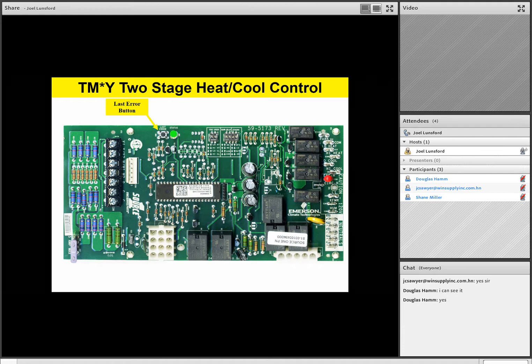Right next to the last error button, you'll find that it has a status LED. It's going to be the same thing. It'll flash either red, green, or yellow based on the flash code. As we move around the board, you're going to have what we call continuous fan on speed selection. Instead of physical jumpers like we had on our previous board, the TM9Y board that we're looking at now actually has dip switches. You can move those little dip switches to give you a continuous fan on speed selection.